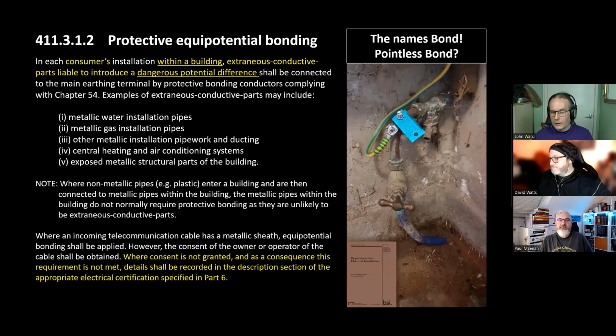Within a building, extraneous conductive parts liable to introduce a dangerous potential difference. And that's a new term, dangerous potential difference, because you can get potential differences. I can get my Megger out and go somewhere at work and read voltages, but they will all be 4 or 5 volts, and that's fine. It's tolerable, but it depends on the nature, utilization, the system, what's being leaked to earth, what the local network conditions are. So it has the same stuff to be bonded.